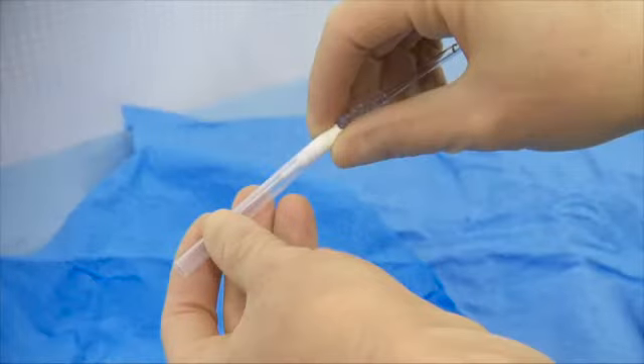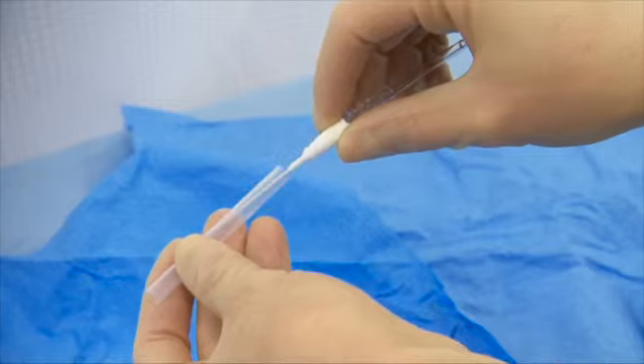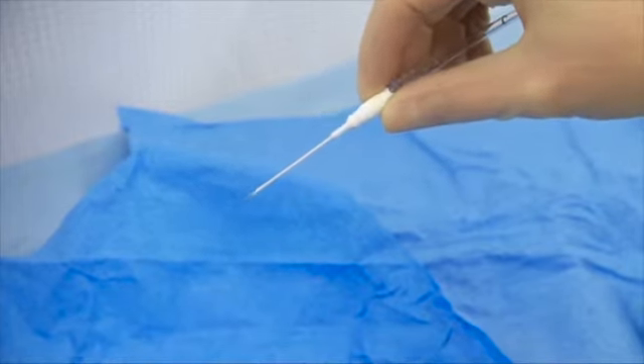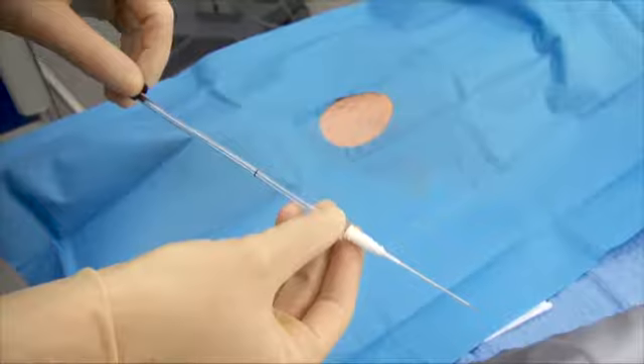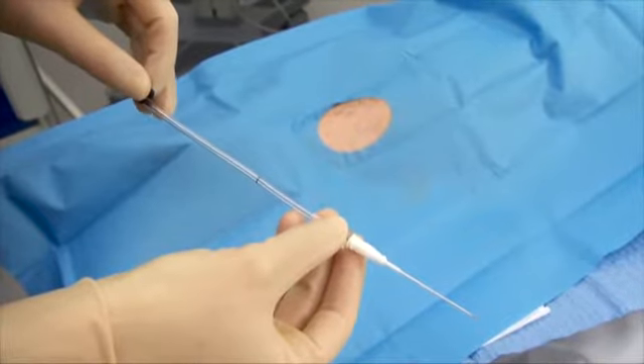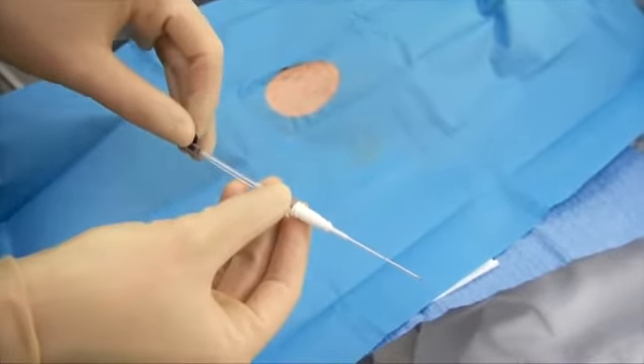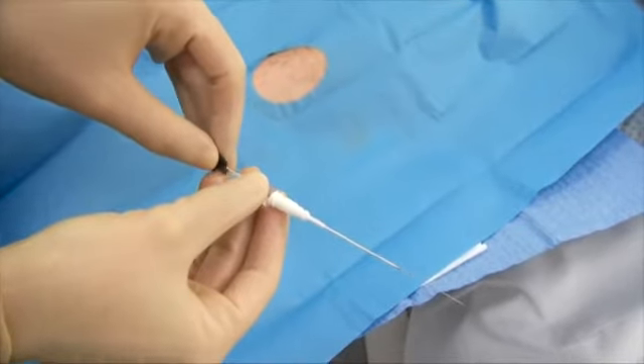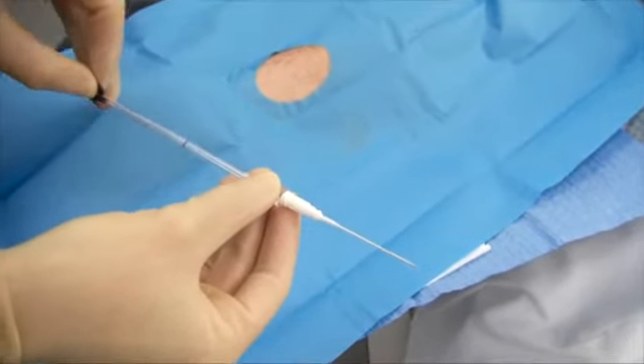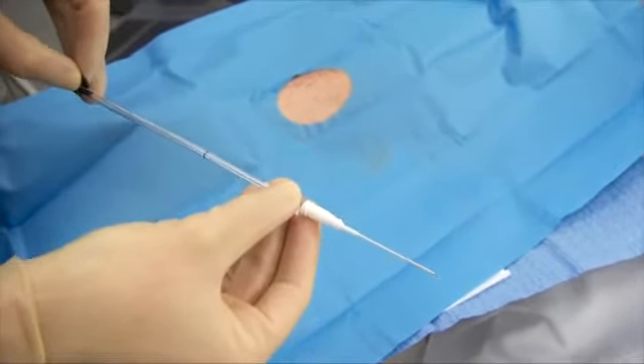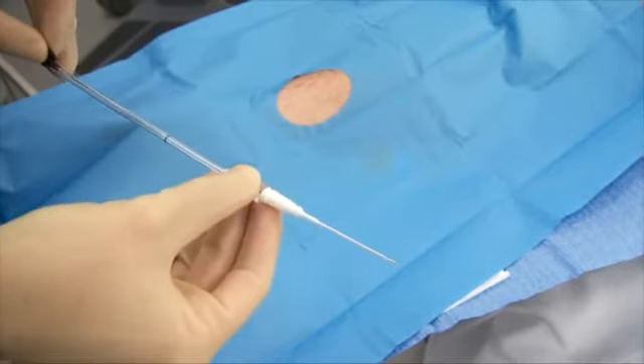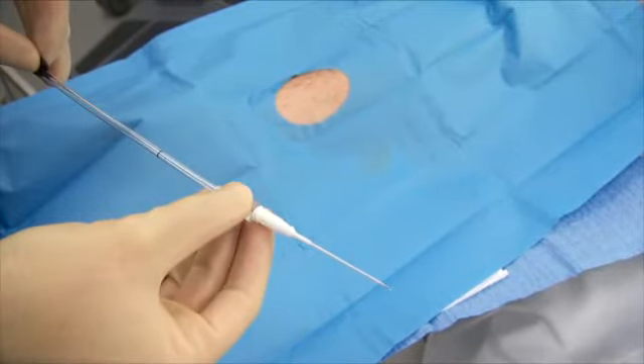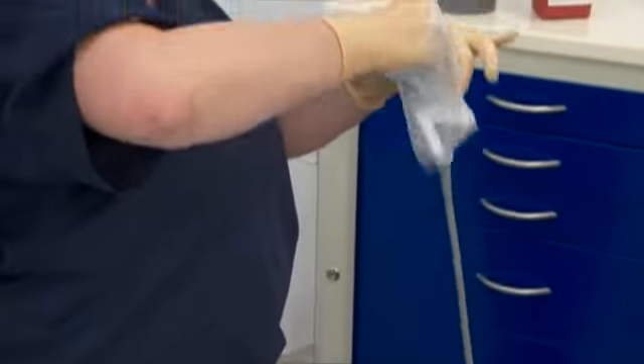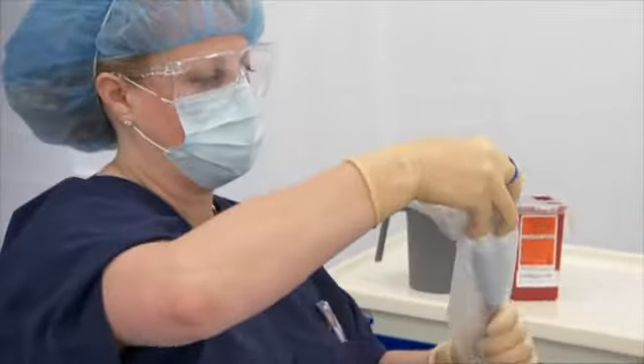Now, we will review the catheter prior to insertion. Remove the protective shield from the placement device. Be sure to test the advancement and retraction of the spring wire guide through the needle using the spring wire guide handle to ensure proper function. Note: prior to insertion, the spring wire guide handle must be returned to the original position before insertion, or blood flashback may be inhibited. Next, don sterile probe cover using sterile technique.